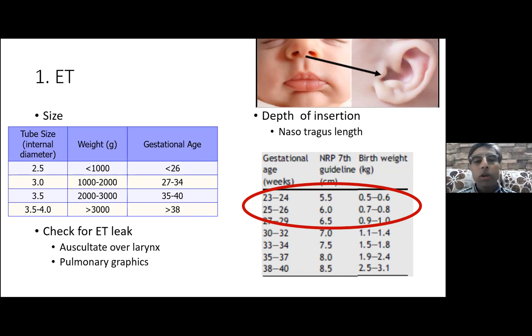If the leak is minimal, you may not pick it up clinically, but pulmonary graphics, as Dr. Tejo has put it out, will help you pick up whether there is a significant endotracheal leak or not. If there is a very slight leak, for example 10% or 15%, it doesn't matter, because most of the new generation ventilators compensate for a certain amount of leak. But if a significant leak is there, then whatever pressure you have set may not get delivered to the baby. Whatever volume or flows you have set may not actually be entering the lungs. So you should be careful when there is a significant leak.